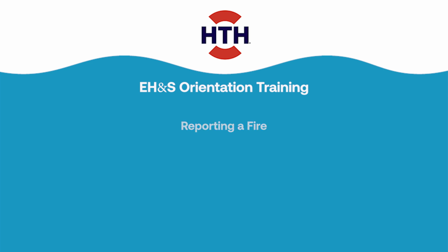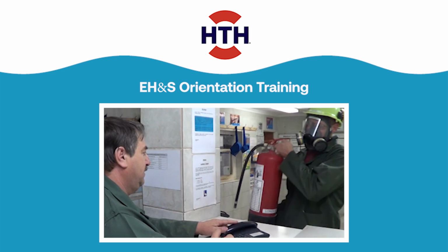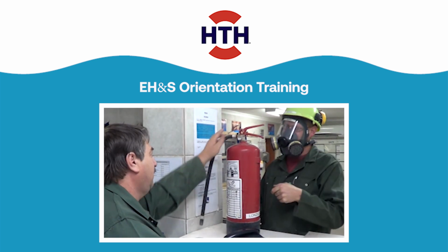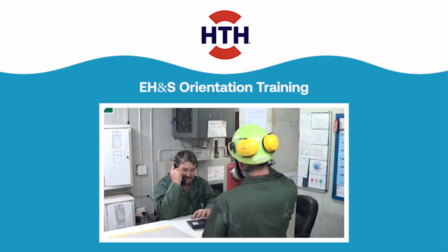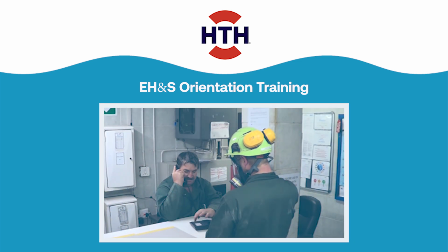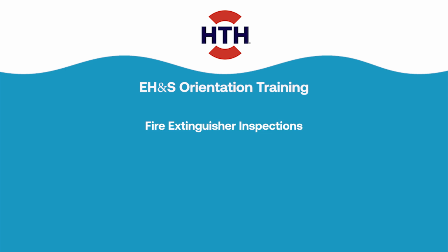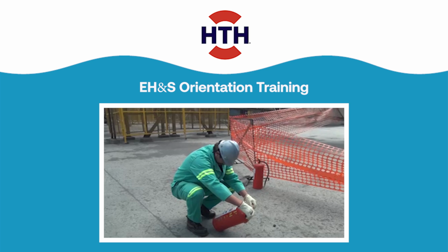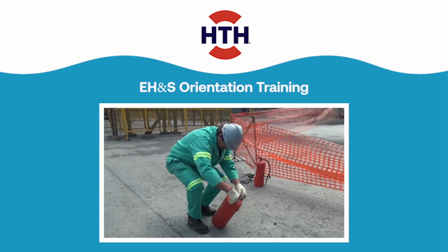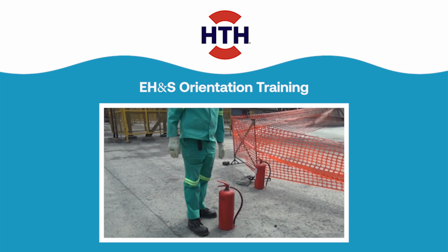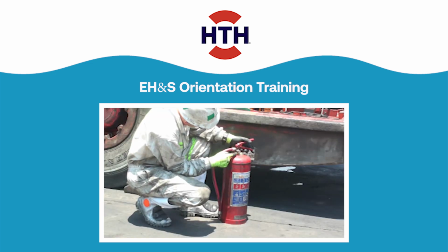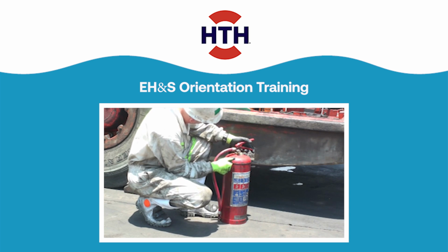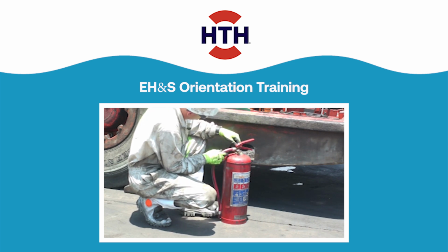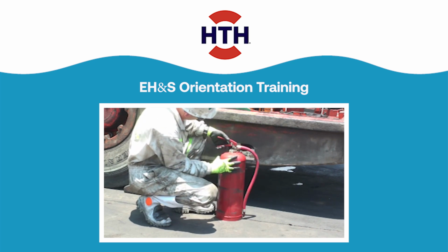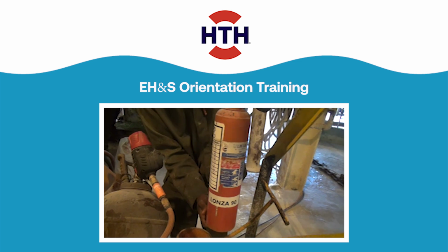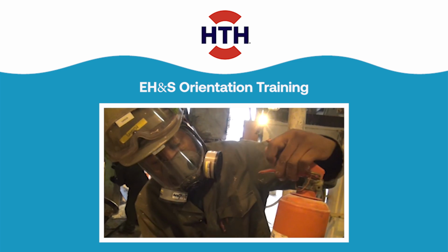Reporting a fire. Important. Whenever a fire extinguisher was used, report the reason for use immediately to your supervisor and the EH&S department for investigation. Fire extinguisher inspections. Like any mechanical device, fire extinguishers must be maintained on a regular basis to ensure their proper operation. You, the owner or occupant of the property where fire extinguishers are located, are responsible for arranging your fire extinguisher's maintenance. Fire extinguishers must be inspected or given a quick check every 30 days.